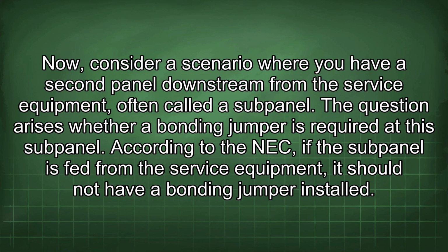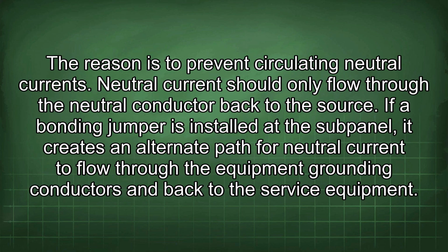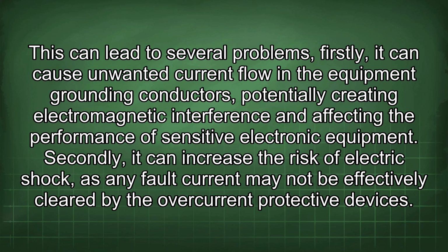subpanel. The question arises whether a bonding jumper is required at this subpanel. According to the NEC, if the subpanel is fed from the service equipment, it should not have a bonding jumper installed. The reason is to prevent circulating neutral currents. Neutral current should only flow through the neutral conductor back to the source. If a bonding jumper is installed at the subpanel, it creates an alternate path for neutral current to flow through the equipment grounding conductors and back to the service equipment. This can lead to several problems.